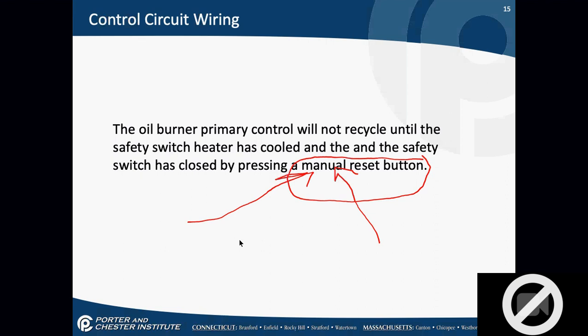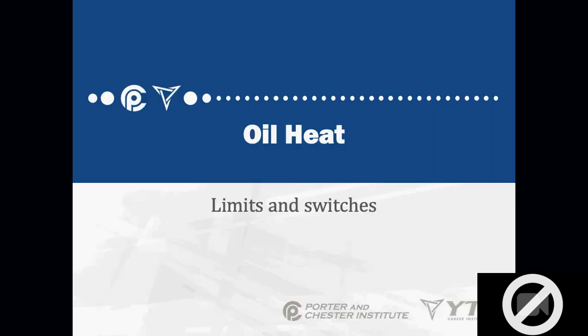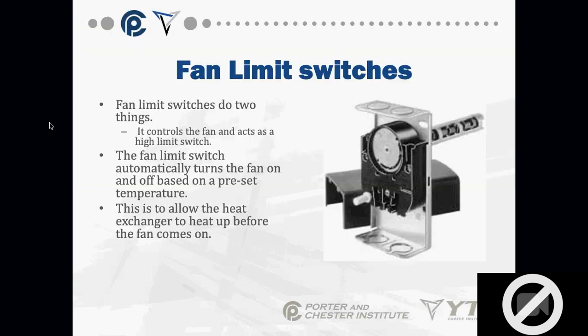We have to talk about them because they still appear on state licensing exams, but we need to realize that they're going away. Okay, so control circuits of oil systems are actually somewhat easy. There's not a lot to them. But one of the primary parts of the control system of an oil furnace is the limit switch. The high limit switch is a primary component of our safety devices.